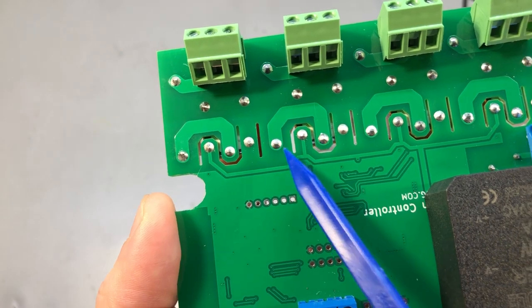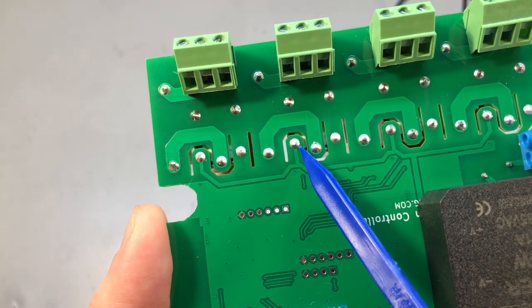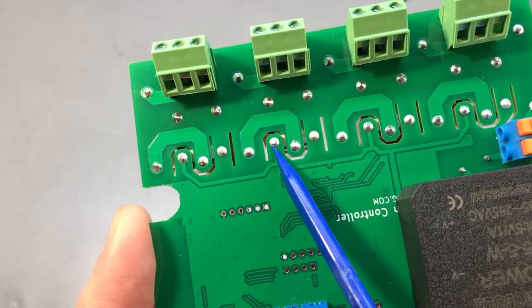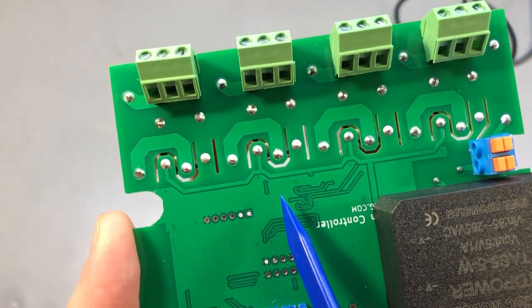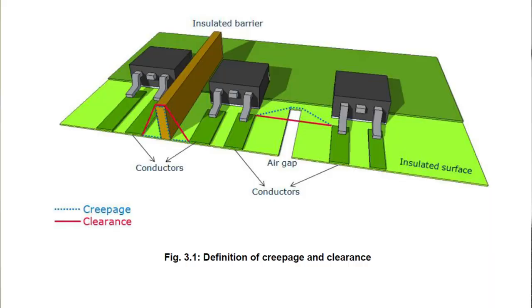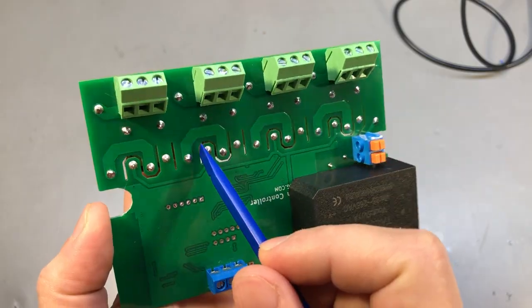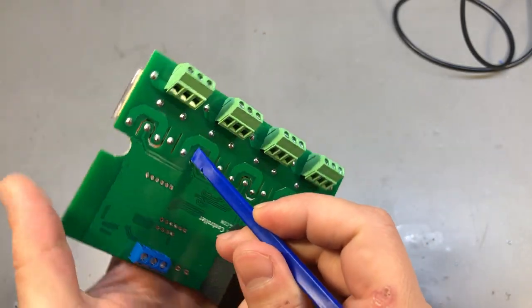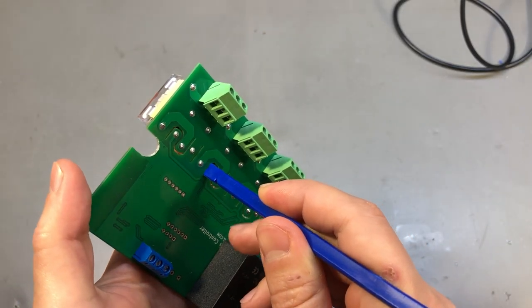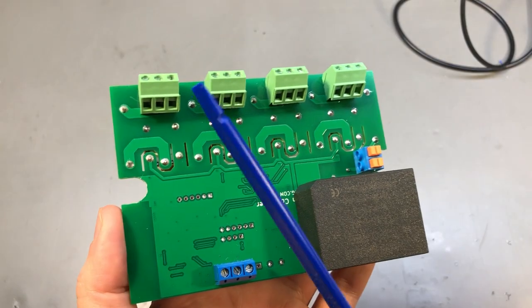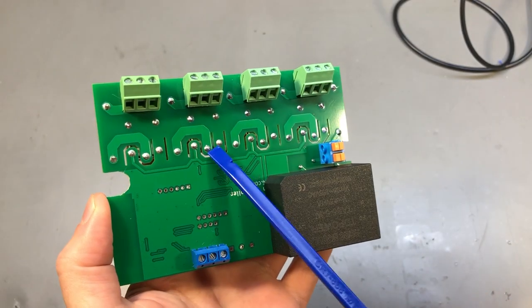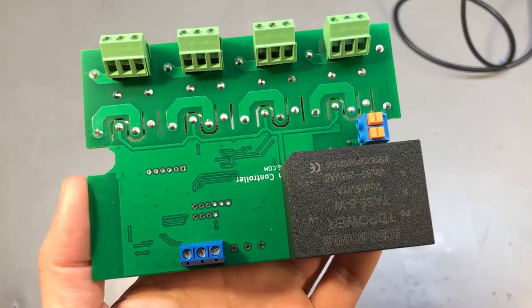So by adding this cutout here we have basically increased the creepage distance which now needs to go around the cutout. But if you'd also like to increase clearance, you will need to add some kind of a barrier that goes into this slot and physically prevents any arcing through air between those two points. And this can usually be built into the enclosure like some plastic walls and they will slide through the cutouts creating a barrier.